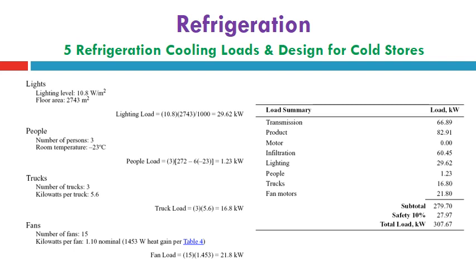Transmission load total from the previous slides is 66.89 kilowatt, product load 82.91, motor load is 0, there is nothing listed about it. The infiltration load 60.45, lighting 29.62, people 1.23, trucks 16.8, fan motors 21.8, from here the subtotal. And finally he takes another safety factor for the total, from the subtotal to get the total load in kilowatt as 307.67 kilowatt, the total refrigeration load of this cold store.